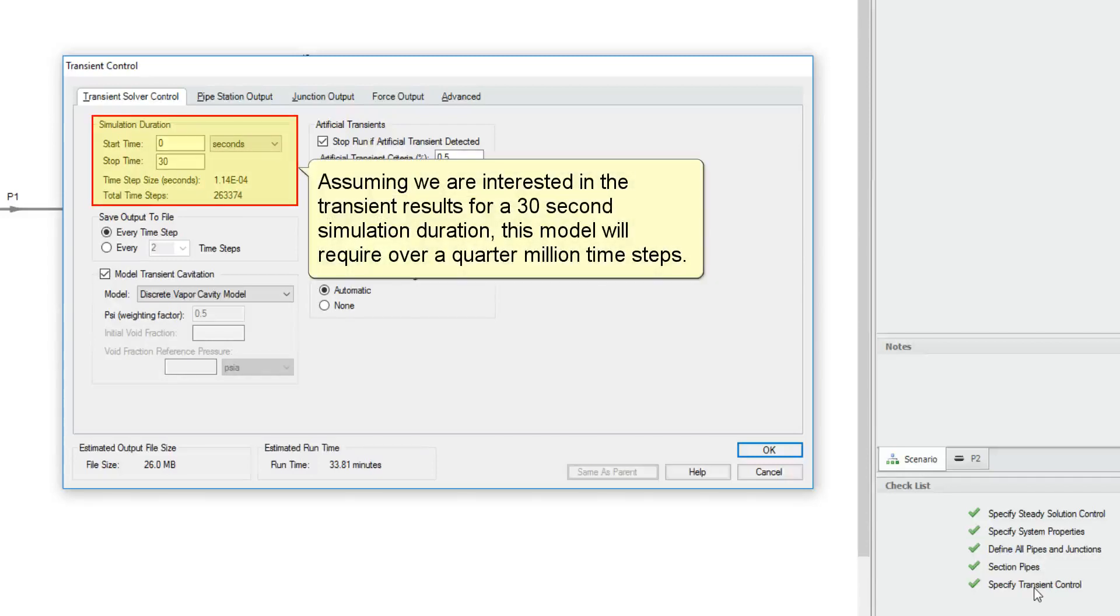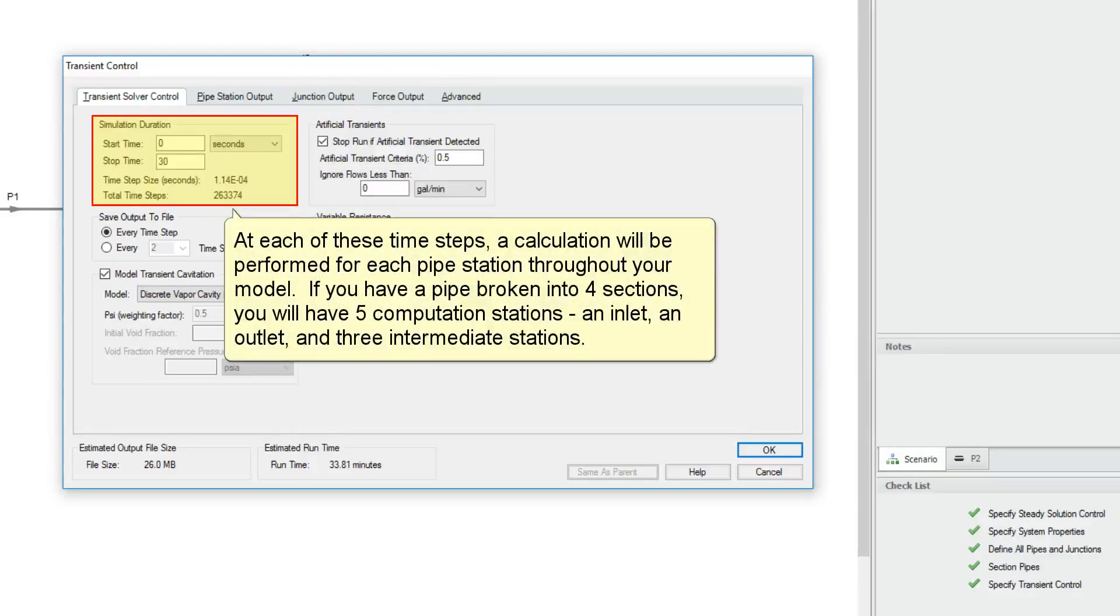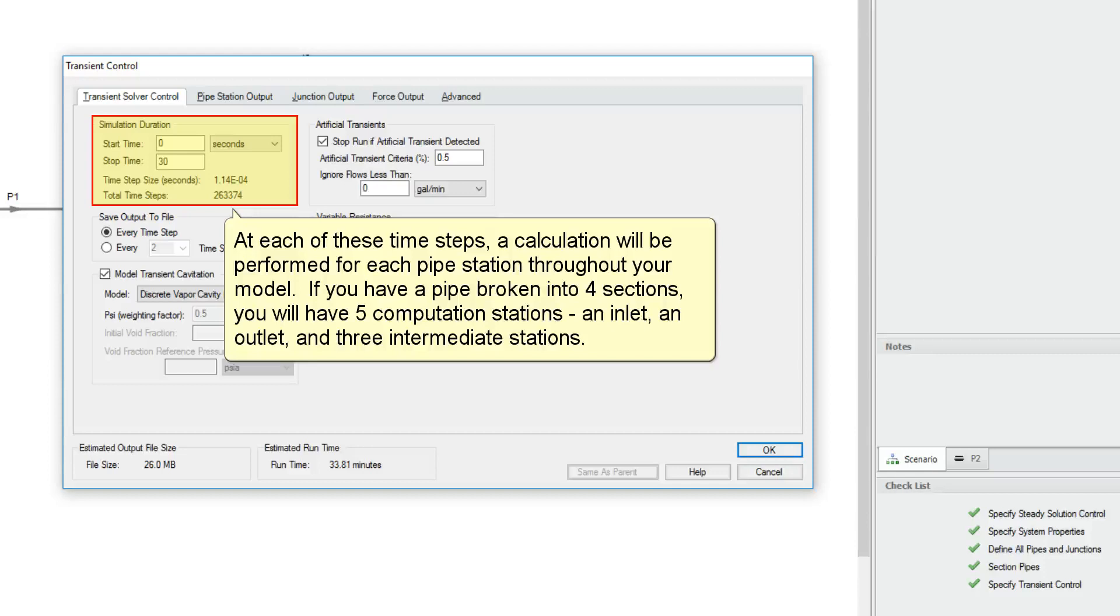Assuming we are interested in the transient results for a 30 second simulation duration, this model would require over a quarter million time steps. At each of these time steps, a calculation will be performed for each pipe station throughout your model. If you have a pipe broken into four sections, you will have five computation stations: an inlet, an outlet, and three intermediate stations.